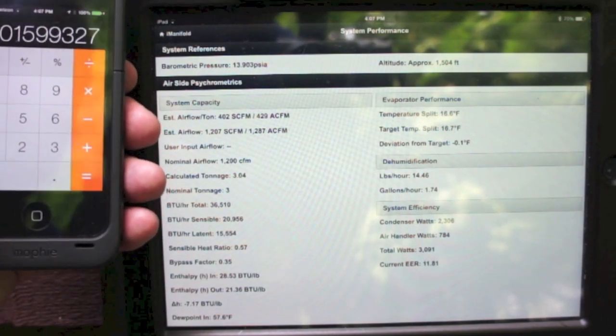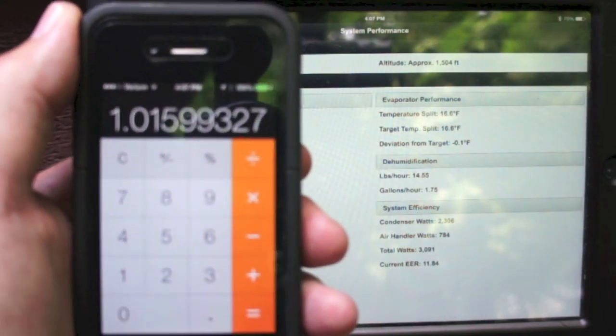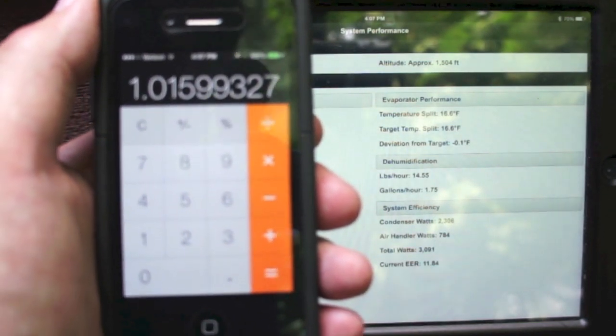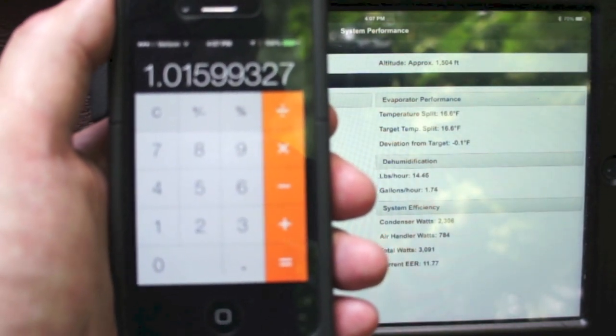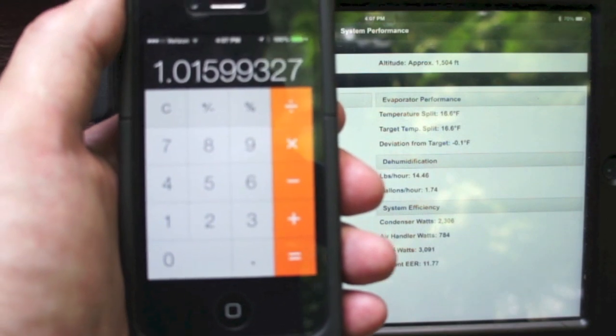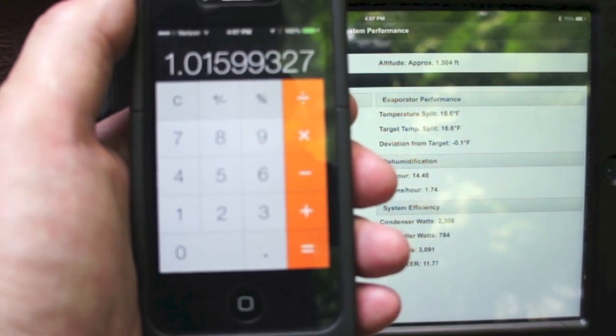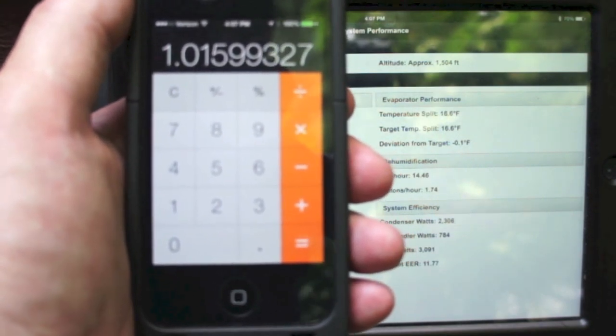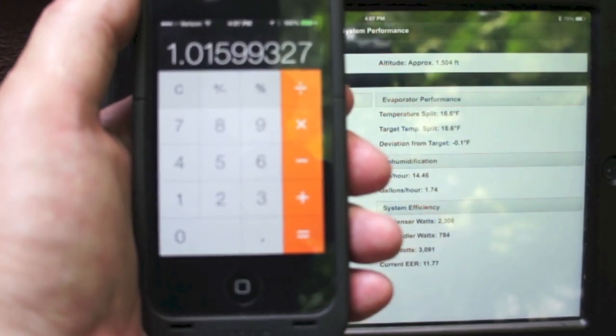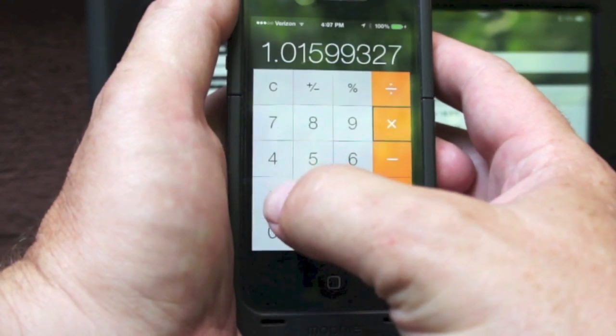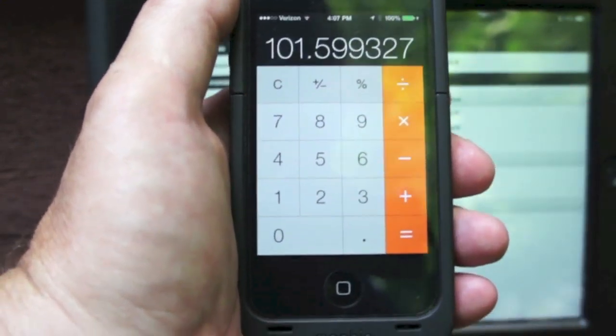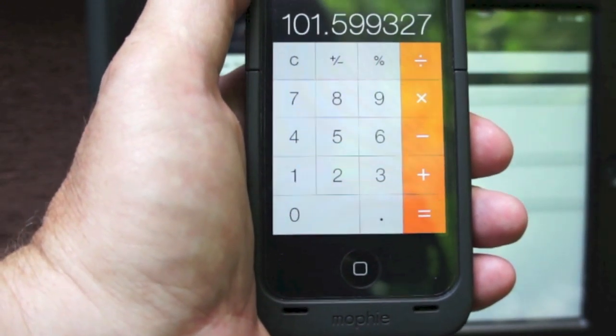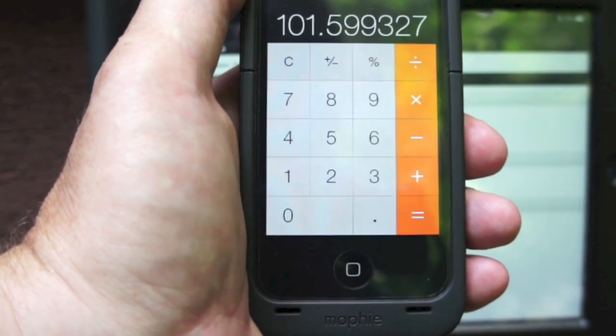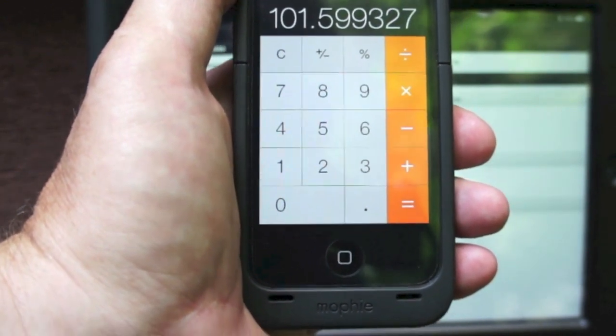equals 1.01. So that means we're calculating 101% of our airflow reading with the iManifold and 2 wireless probes. So we are within 1% of what our ECM says we're doing. That is pretty darn spot on here. For those of you that don't like math, there we go. So 101% of our airflow, and that is pretty darn close if you ask me.